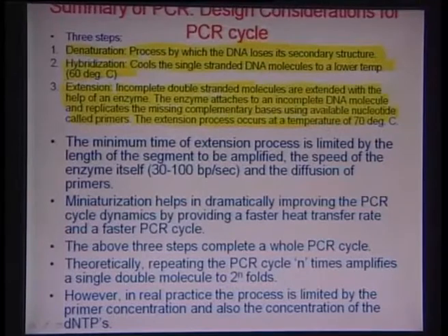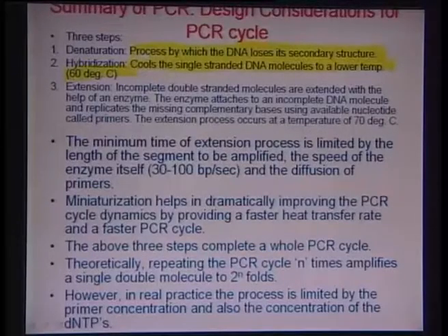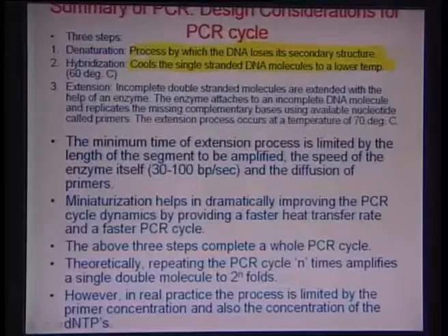So these three temperature states are very critical, okay, and this essentially can be achieved in a thermal cycler, which is conventionally designed in a manner where there is a huge aluminum block, okay, with various through holes, and essentially this is used as a thermal cycling modality for holding together some vials with the PCR fluid in it. And then what happens is that the block is cycled at different temperature points by using a Peltier cooler and a resistance heater.